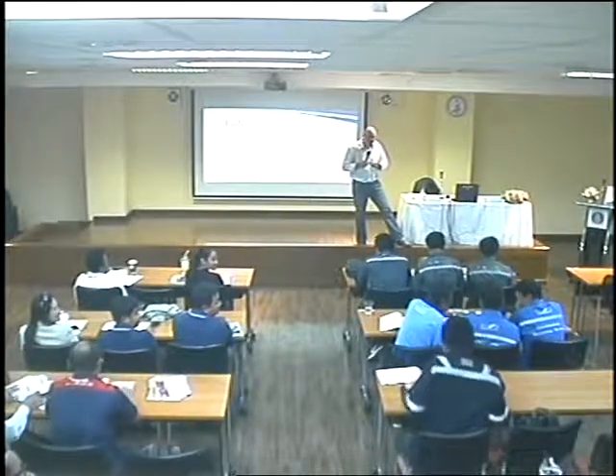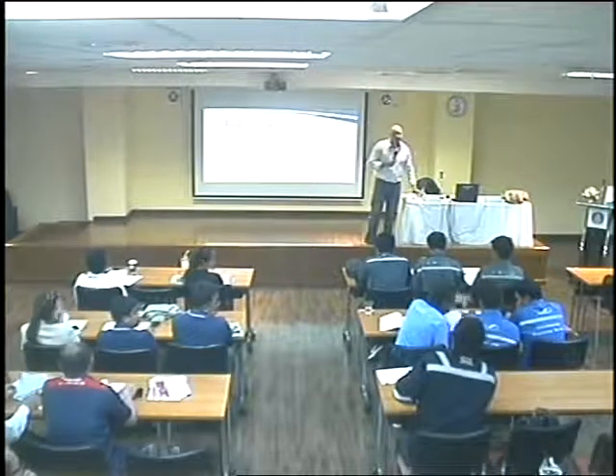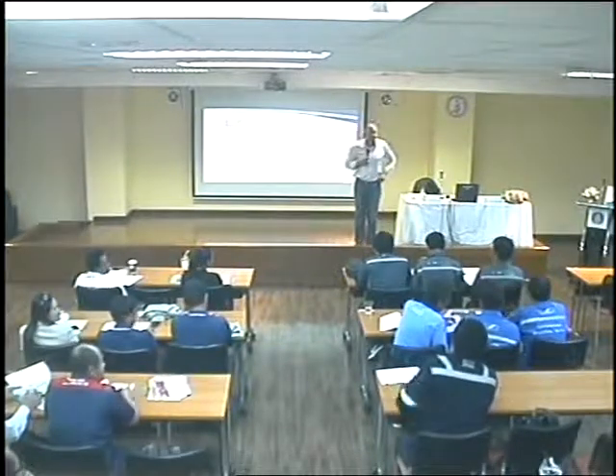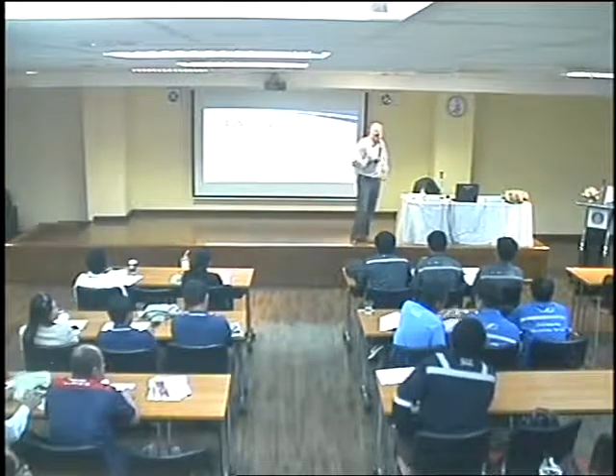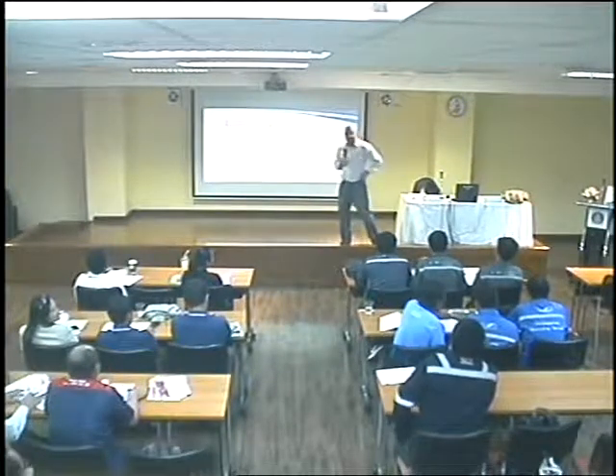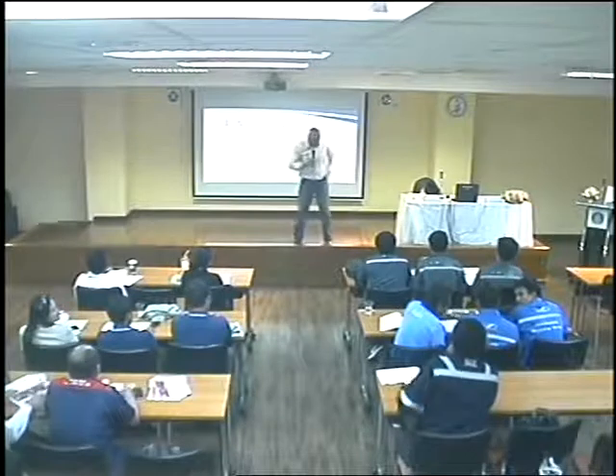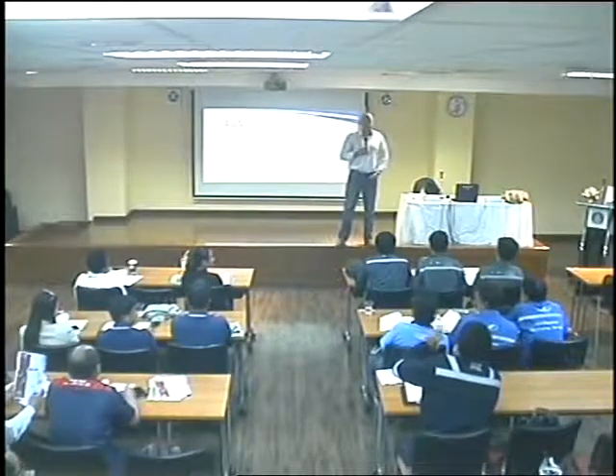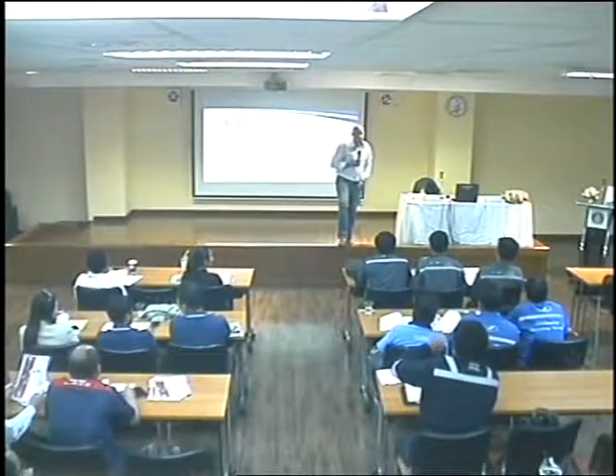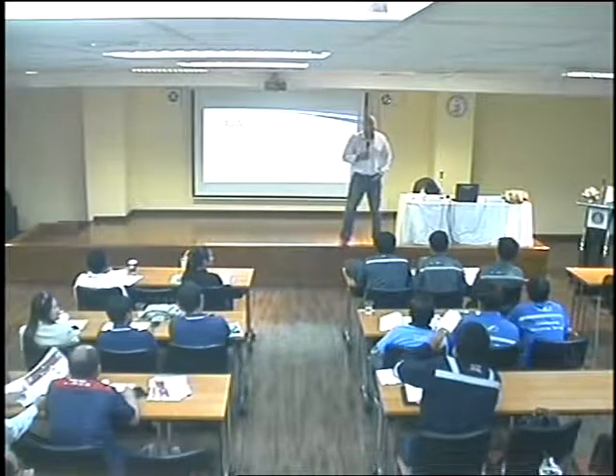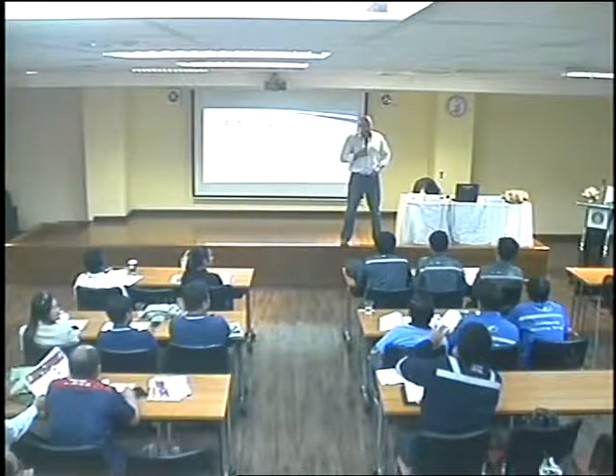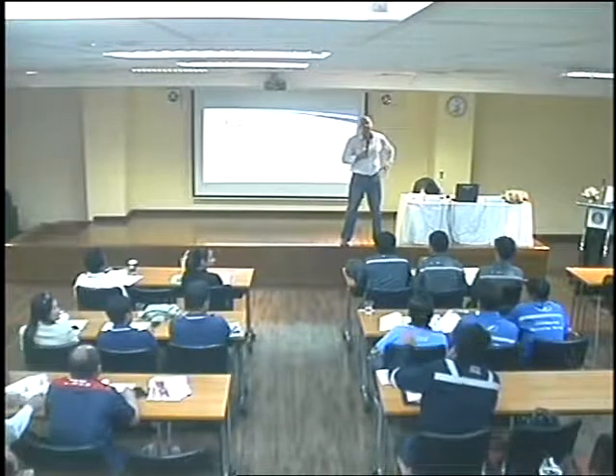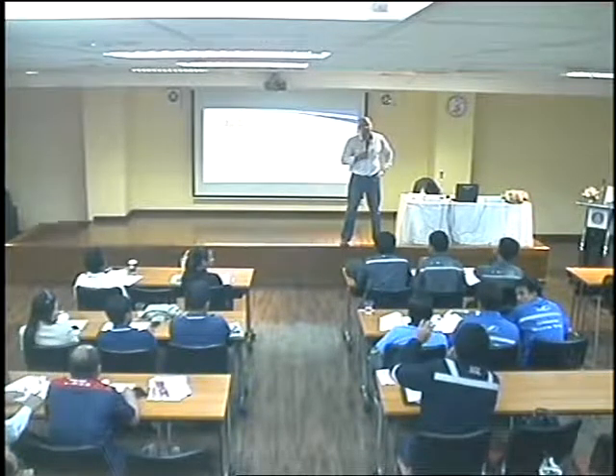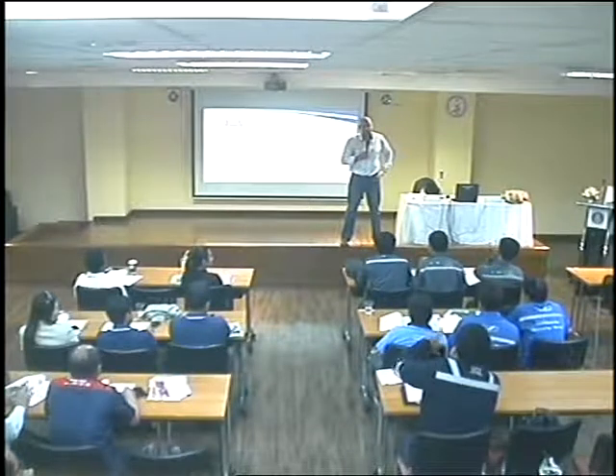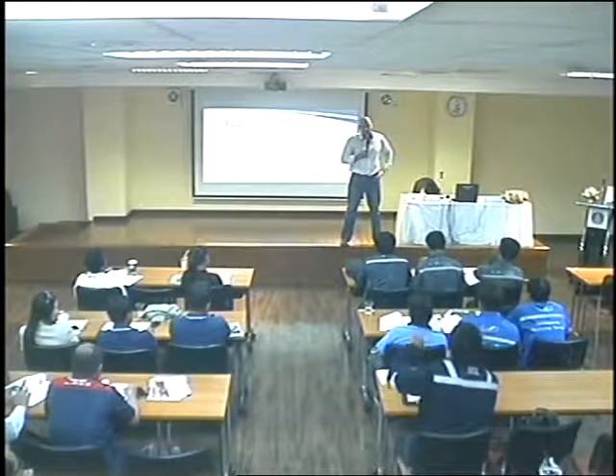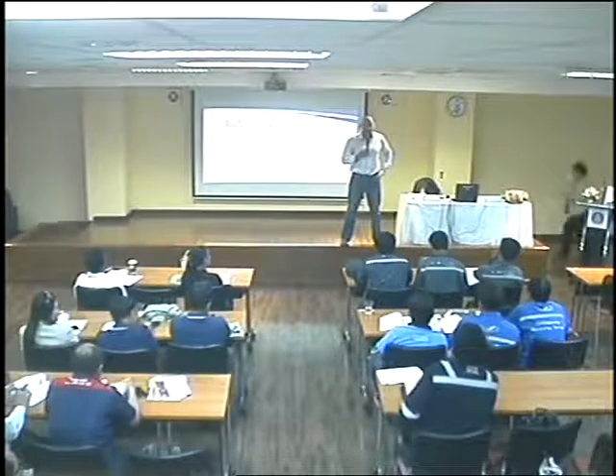Test. Okay, Mr. Mika, I have some questions about the new APEC instrument. Sure. Yeah, because I'm worried about the sample pump of the APEC instrument because the new one is a smaller one, right? I worry about the capacity of the vacuum head of the sample pump when we're sampling on a stack that has a pressure of around minus 200. Is it available for sampling on that condition or not? It is. It should be okay.